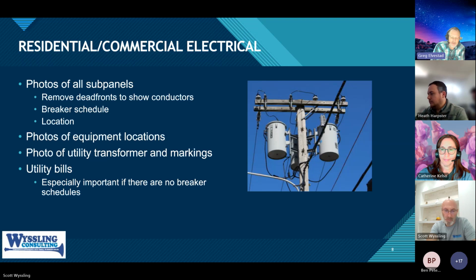Breaker schedules are a code requirement. Now, some buildings have been up since dirt was new - they won't necessarily have good breaker schedules. You want to make sure to attempt to locate those, but the sizes of the breakers is very, very helpful.